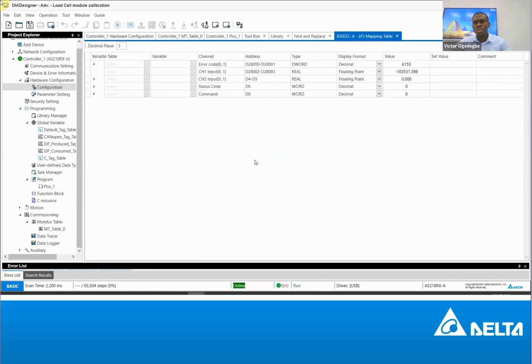You can see the value. So this is the weight, the digital value. You will not see voltage. In the module, you only see the digital equivalent. What the module does is convert the analog signal from the sensor to a number. I can tell my PLC, if you see this number, stop filling the package. If you see this number, stop doing this. So based on this number, you can program the algorithms of your machine. You understand? So it gives you a number.